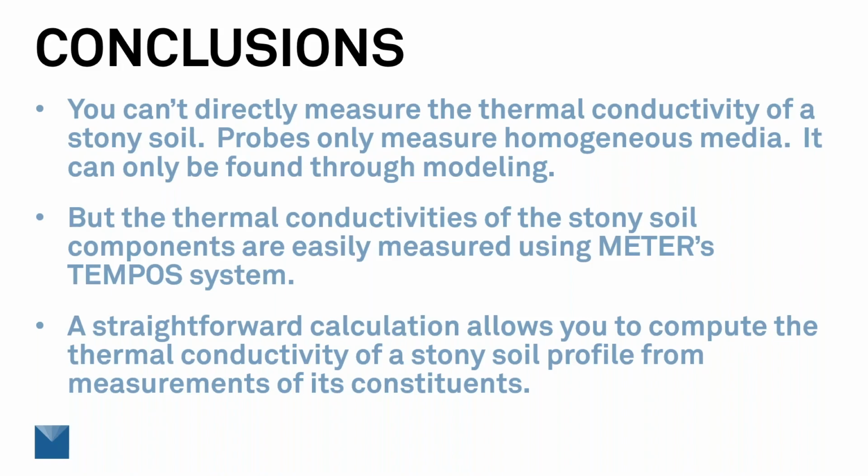Here's another question, Dr. Campbell. Do I need to measure the thermal conductivity of the rocks as they are in the soil, or can I just find out their values from the internet and just use those values? Well, certainly taking into account the fact that there is both soil and rock will give you a lot better number than if you don't take that into account.